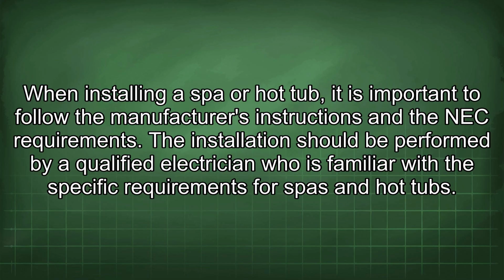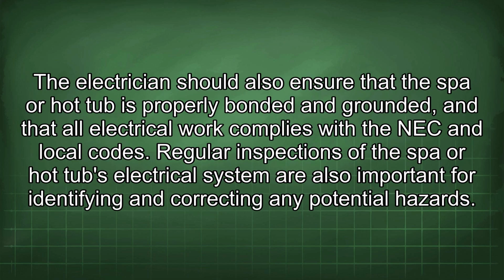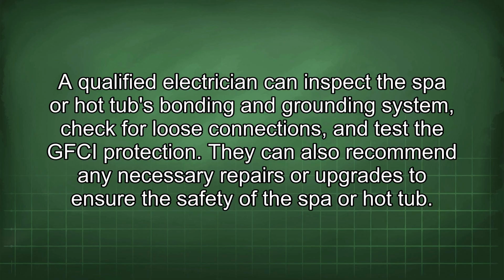The installation should be performed by a qualified electrician who is familiar with the specific requirements for spas and hot tubs. The electrician should also ensure that the spa or hot tub is properly bonded and grounded, and that all electrical work complies with the NEC and local codes. Regular inspections of the spa or hot tub's electrical system are also important for identifying and correcting any potential hazards. A qualified electrician can inspect the spa or hot tub's bonding and grounding system, check for loose connections, and test the GFCI protection. They can also recommend any necessary repairs or upgrades to ensure the safety of the spa or hot tub.